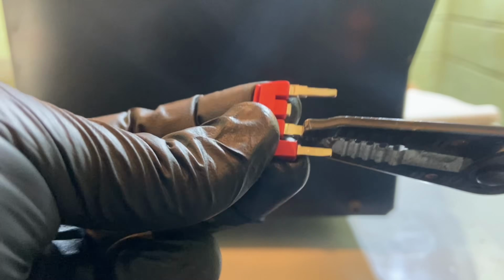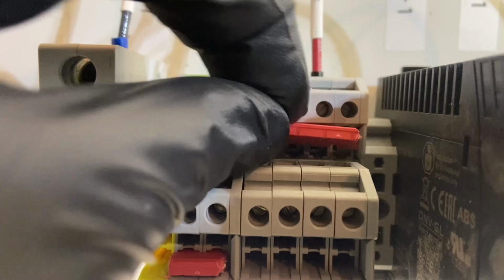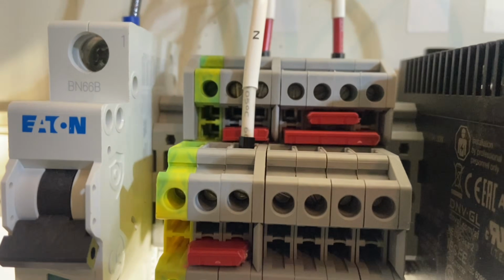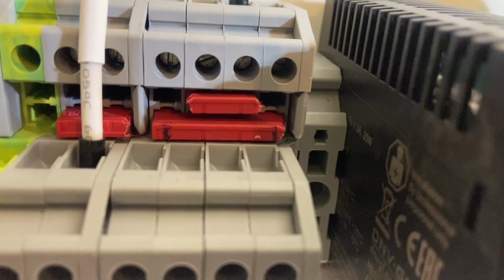Here I had to add a jumper, and I wanted to show you guys, if you have to jump across terminal blocks with a jumper, that's how Phoenix Contact recommends you do it, and you're supposed to put these little Sharpie marks to indicate that you broke the middle out.